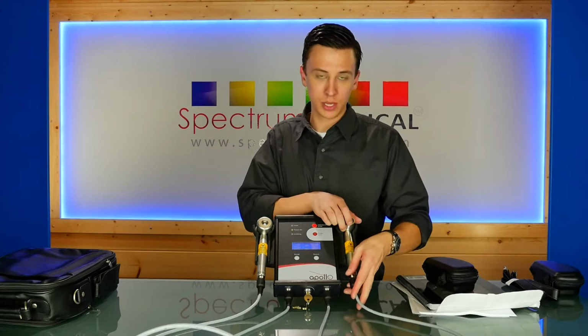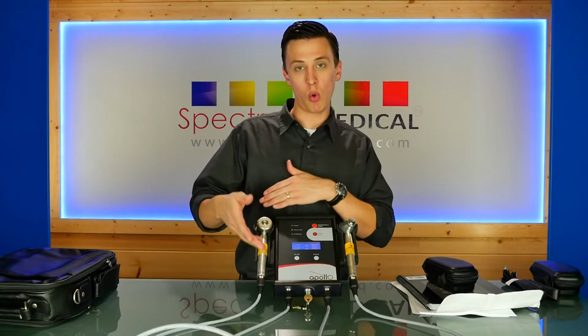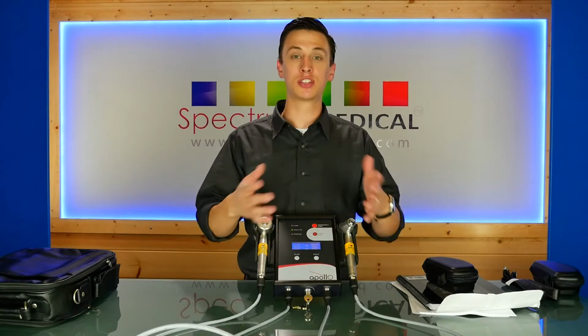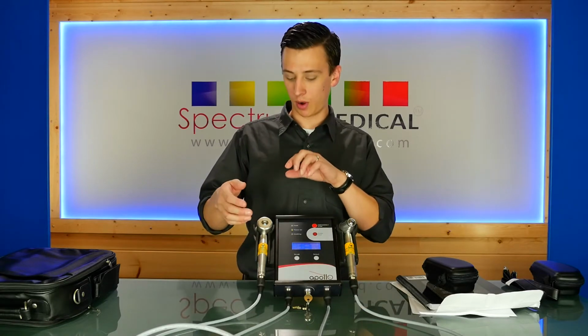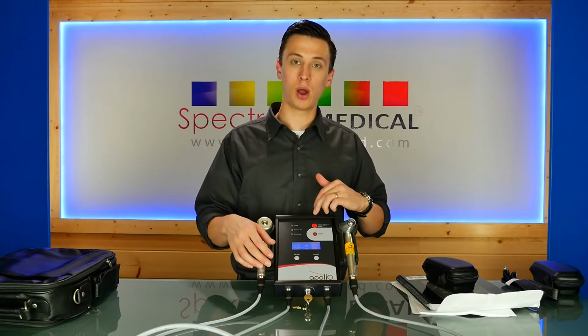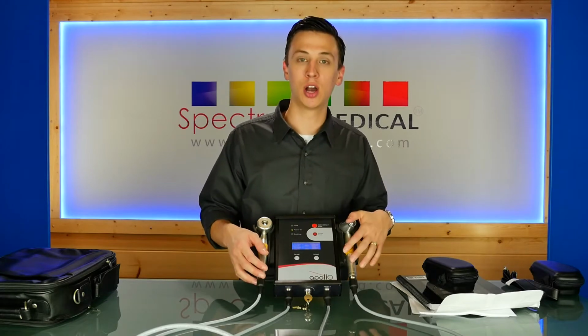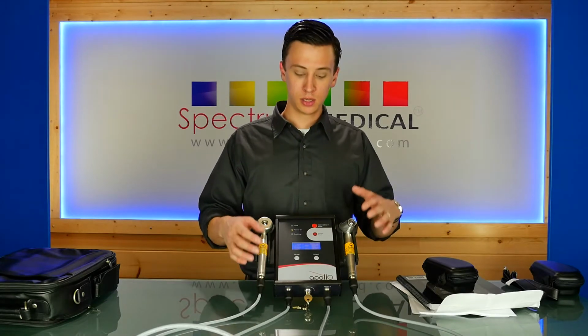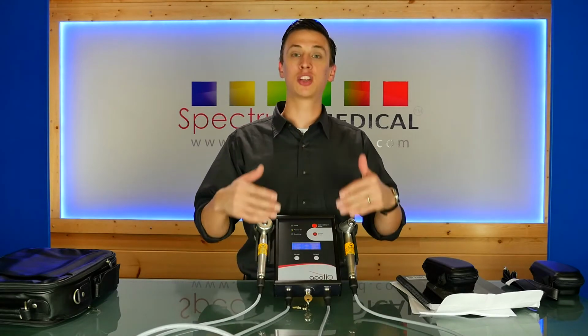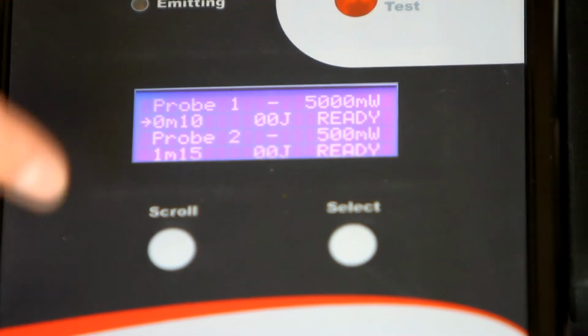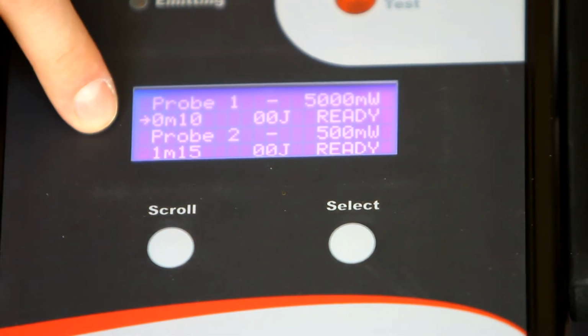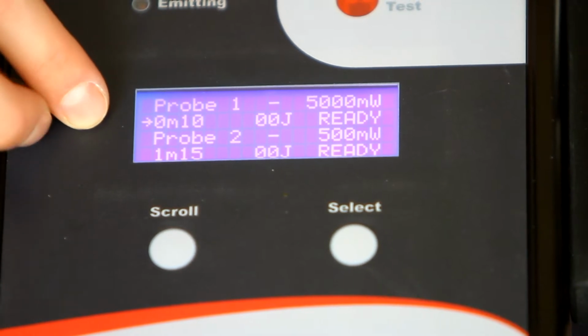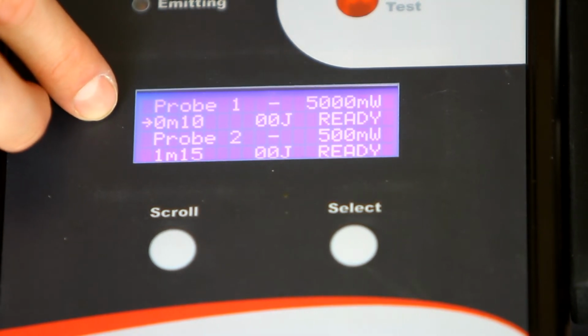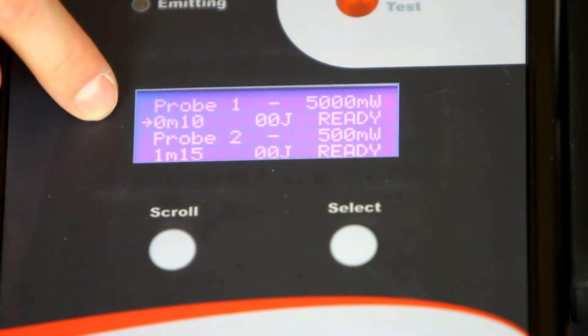Since this is a 2-channel laser probe unit, you have your choice. Do you want 1 probe or 2? You can make your selection from their offerings. They range from 5 watt, 4 watt, 3 watt, 2 watt, and the 500 milliwatt. So there's a little bit of setup before we actually begin treatment. On the LCD screen readout, you're going to see an arrow indicating probe 1 and a 0M10, which is going to indicate 0 minutes 10 second treatment time.